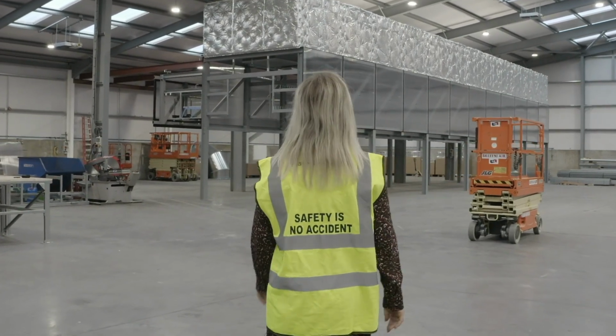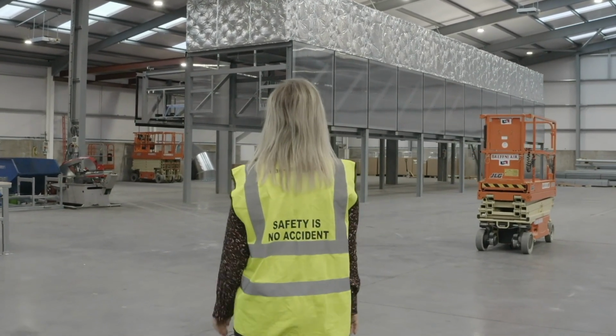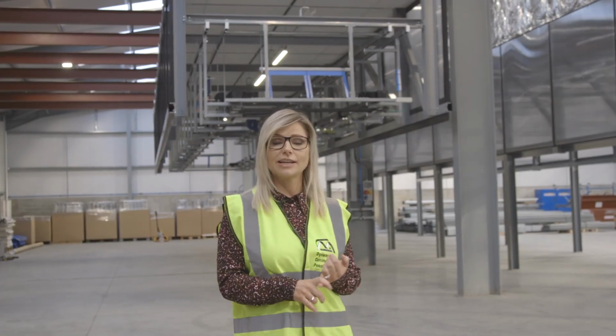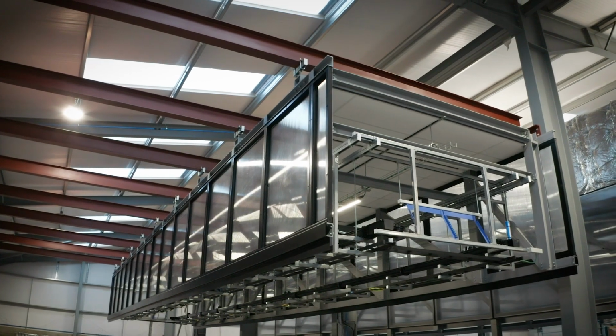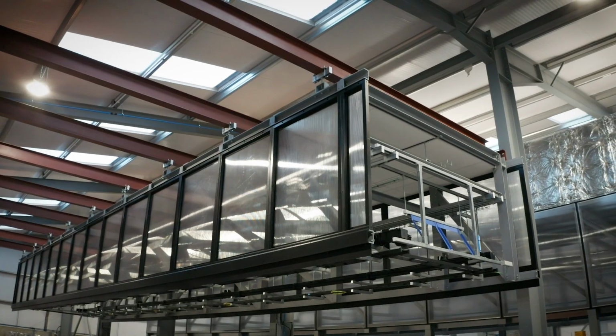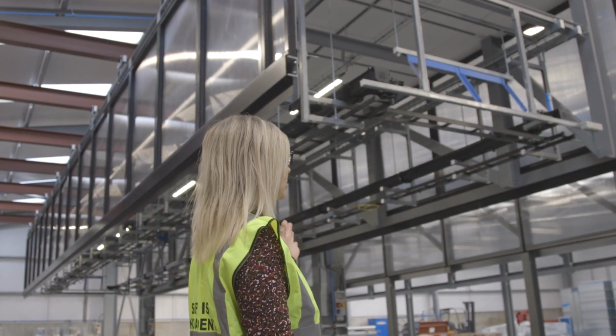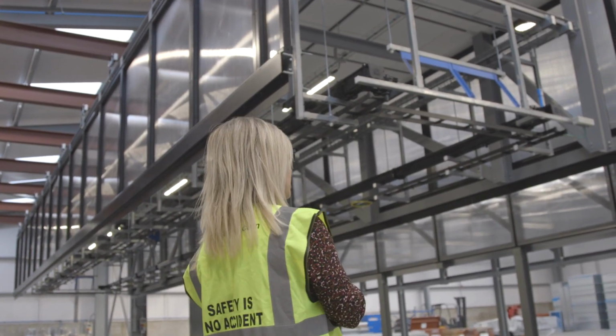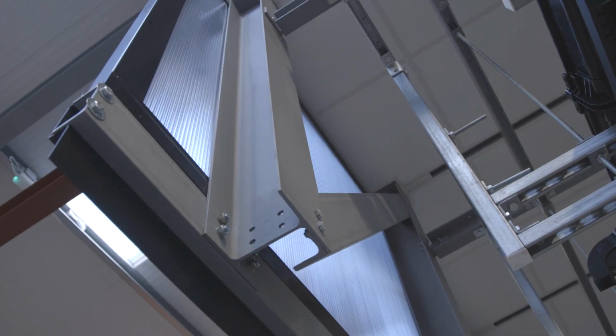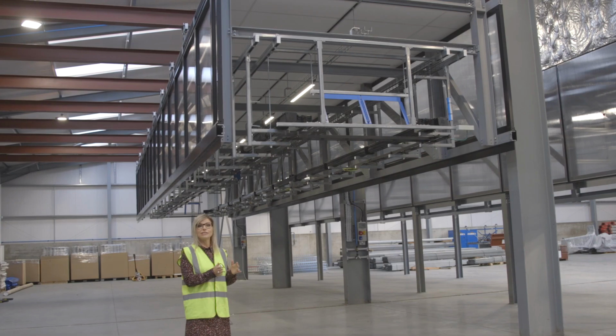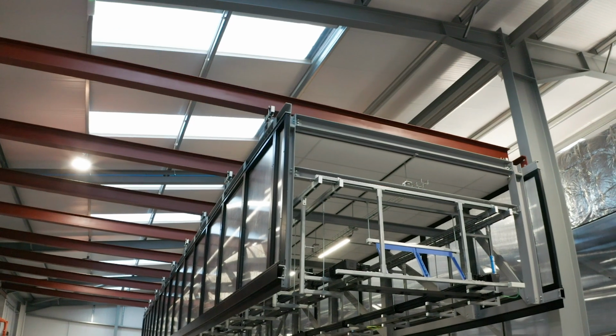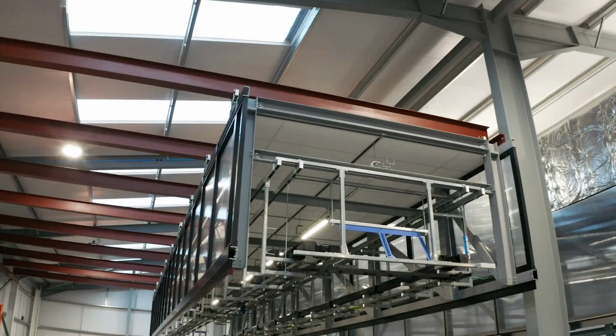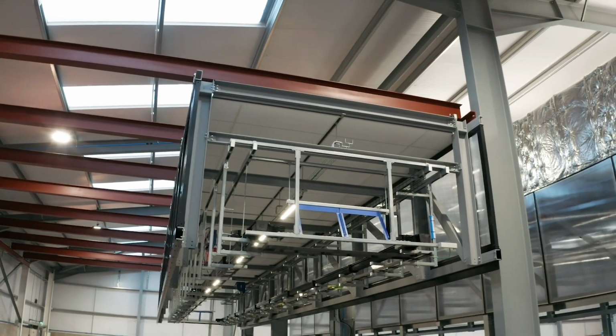Traditional construction is very different to modular construction, but modular construction complies with the same certification and regulation and uses the same materials. The modular combined hot and cold aisle containment unit is prefabricated off-site of structural steel and unistrut frame, and it arrives to the data hall fully complete with all electrical and mechanical components, polycarbonate sides, ceiling tiles and full containment.